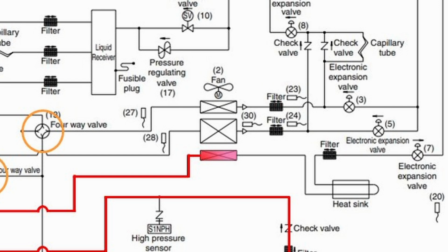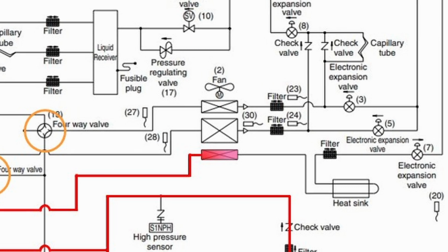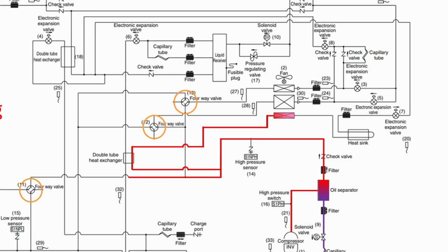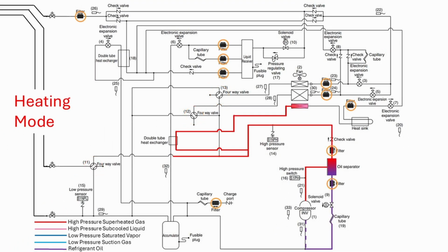In this example, the system is in 100% heating mode. So the 4-way valves will direct the refrigerant to the outdoor heat exchanger, where one small section will be used to cool the inverter board, and it will direct the rest of the high-pressure vapor to the indoor units, where they will be used for heating. You will notice the presence of several refrigerant filters in this system, making a clean refrigerant piping installation even more important.